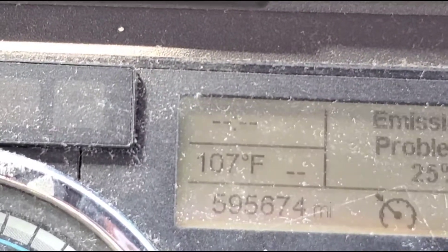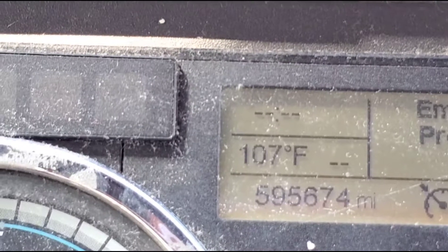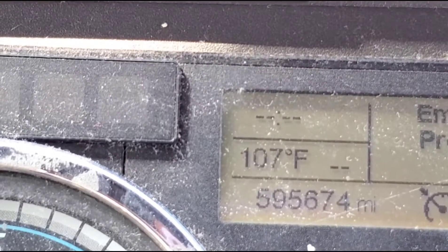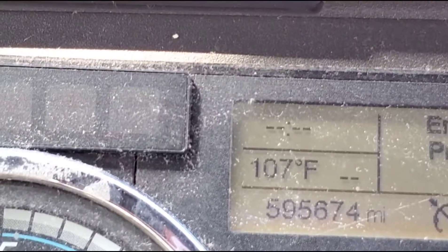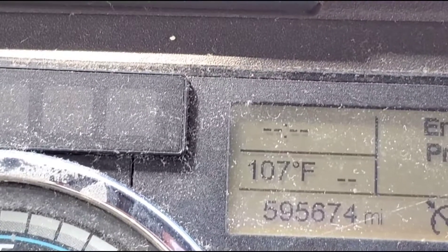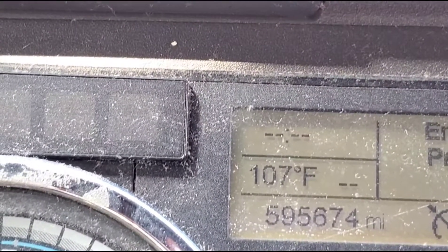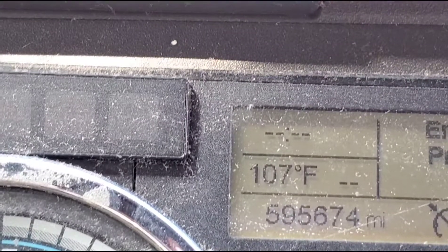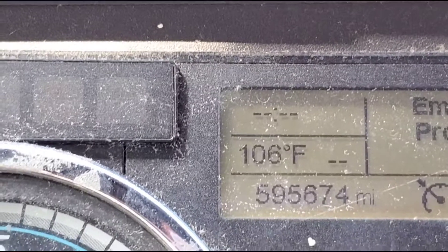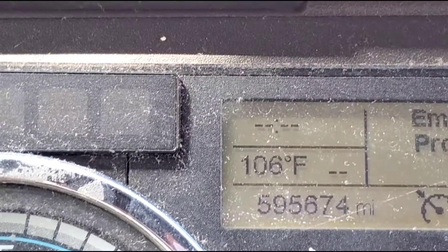This is the temperature inside the truck. The outside temperature is 107 degrees and around 100 degrees at the trailer, and because of that the reefer was having trouble dropping temperature. But it was also a freon issue — the freon was low, and as soon as we added some freon the temperature started dropping.